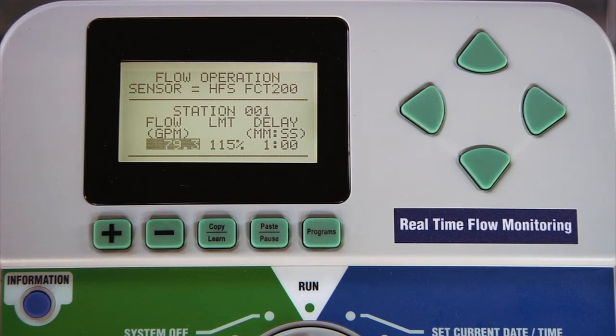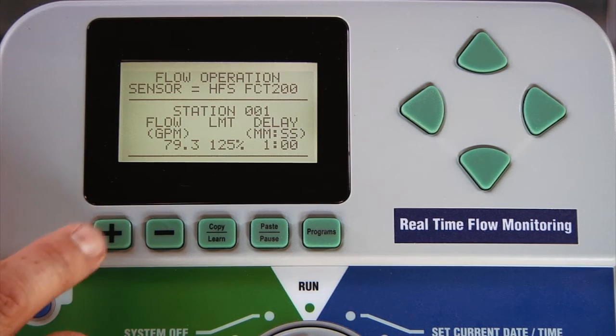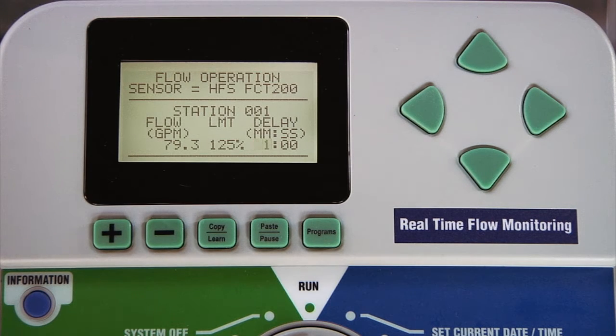Another function you can change is the percentage limit at which the sensor reacts to the overflow. The default for this limit is 115%, which means the sensor will react to overflow conditions when the sensor detects flow values that are 15% over the normal value. We'll go ahead and change that to 125%. Many times city water fluctuates so much that a limit of only 115% may result in false alarms. This limit can be changed by station. The other function you can change is the delay, which is the length of time the controller will wait before reacting to the overflow condition in order to prevent false alarms.